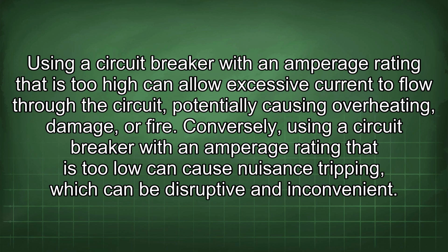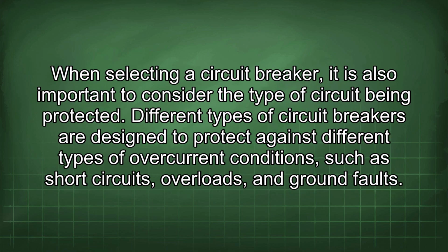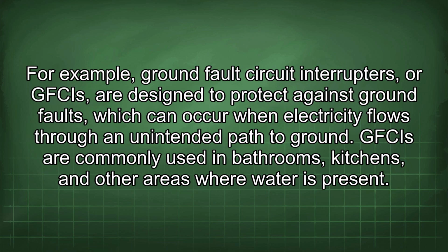Conversely, using a circuit breaker with an amperage rating that is too low can cause nuisance tripping, which can be disruptive and inconvenient. When selecting a circuit breaker, it is also important to consider the type of circuit being protected. Different types of circuit breakers are designed to protect against different types of overcurrent conditions, such as short circuits, overloads, and ground faults. For example, ground fault circuit interrupters, or GFCIs, are designed to protect against ground faults, which can occur when electricity flows through an unintended path to ground. GFCIs are commonly used in bathrooms, kitchens, and other areas where water is present.